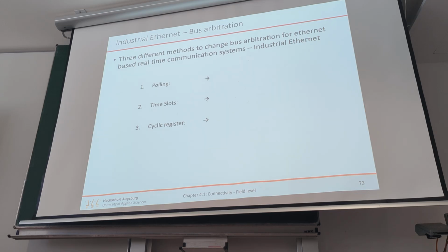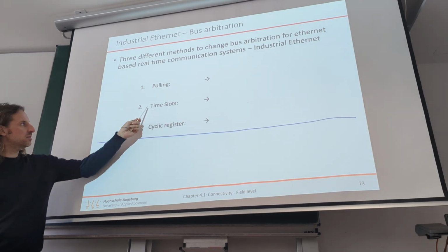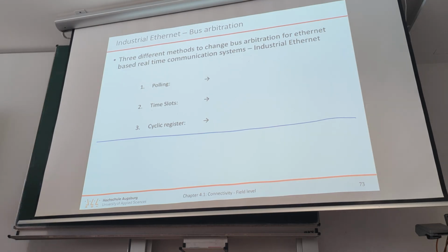Okay, now one of the problems I said is that we don't have that on normal Ethernet. We have a problem with real-time capability, and that's why we extended the bus arbitration in the industrial Ethernet. Industrial Ethernet uses three different approaches: polling, time slot, and cyclic register.